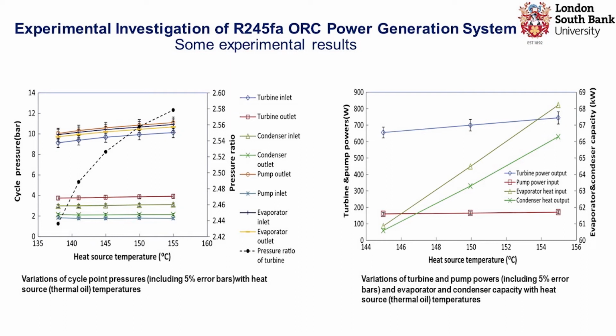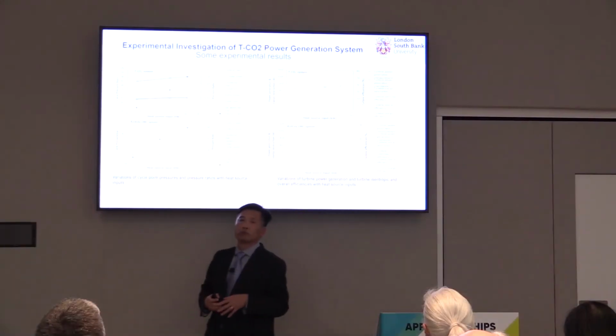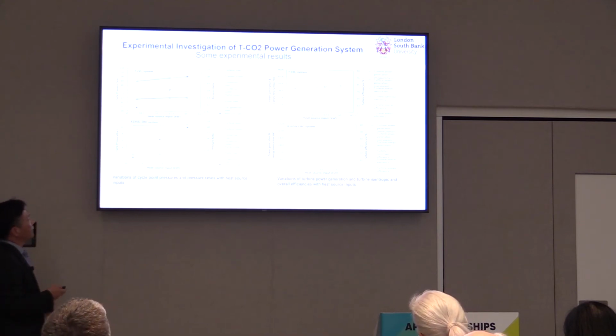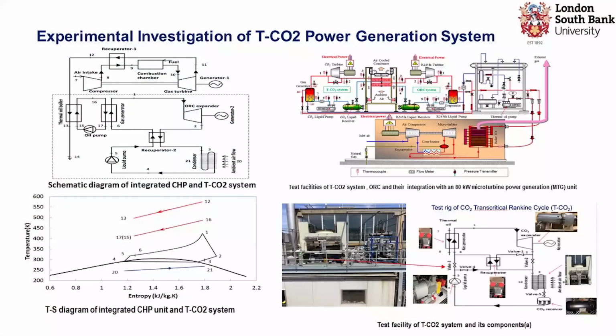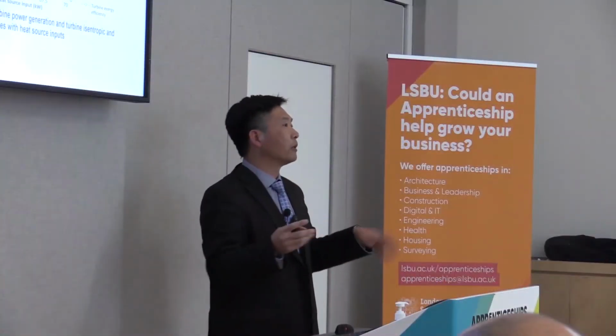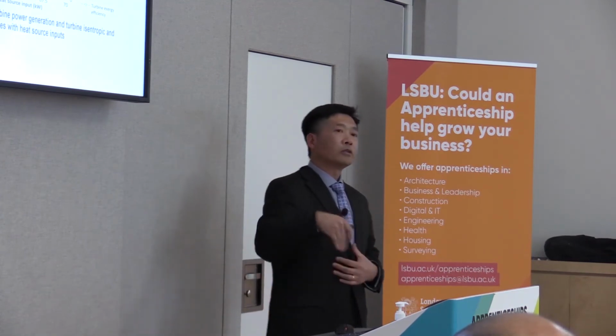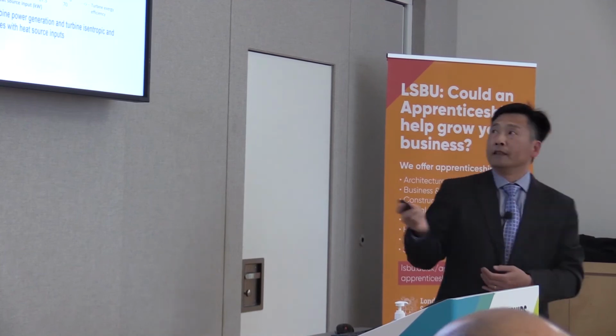I don't want to go into data details because of the time. So the main thing is that you can still use the heat source side, the heat input, to control the pressure in the transcritical CO2 cycle. From what we found from the experimental investigation, it's difficult to compare and evaluate these two systems, one ORC and one CO2 system. The best way is to develop a reasonable model, so that you can have a larger operating range, find out the applicable operating condition for each system, and also optimize each system. So this is why we developed a model.